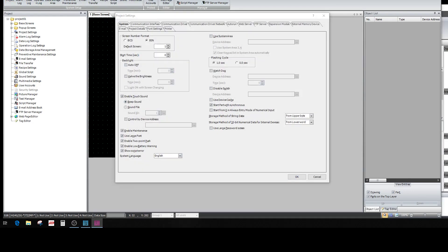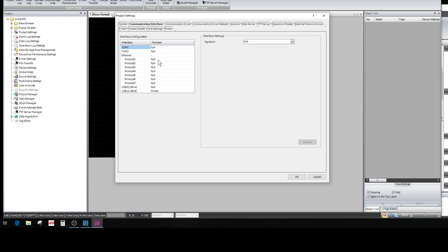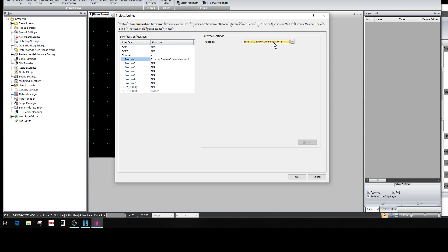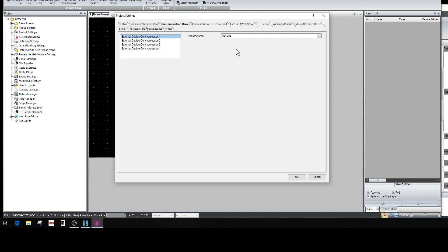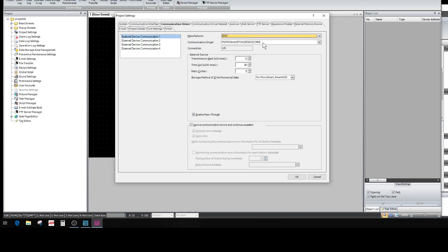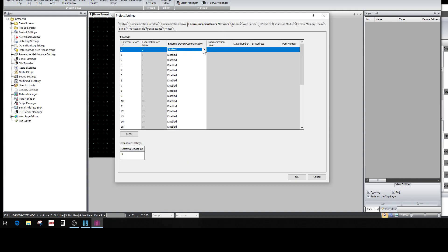First thing we need to do is come over here to Configuration, then Project. We have to set up our communication because if you don't, it won't let you talk to the PLC. So I'm going to do Ethernet protocol. Go to External Device Communication One, pick it over here, then come over here and set the communication driver — pick IDEC. Check this box down here for 232 or 485, but we want to use Ethernet. Communication Driver Network, External Device One — see it fills in at five, meaning we're communicating with 192.168.1.5, which is the PLC. Click OK.